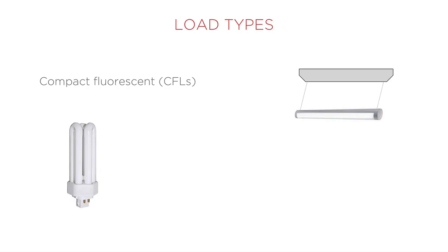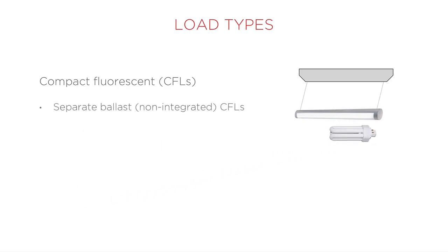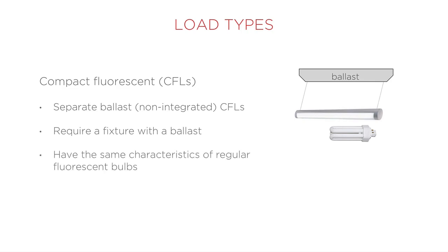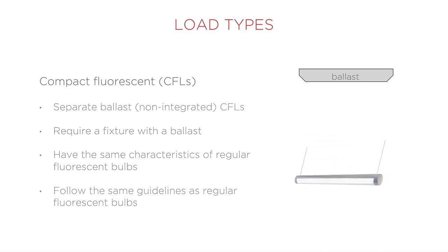Compact fluorescent bulbs. Compact fluorescents, or CFLs, fall into two main categories, those with a separate ballast or an integrated ballast. Separate ballast CFLs require an external ballast within the fixture. Generally, they have the same characteristics as fluorescent bulbs and follow the same guidelines.